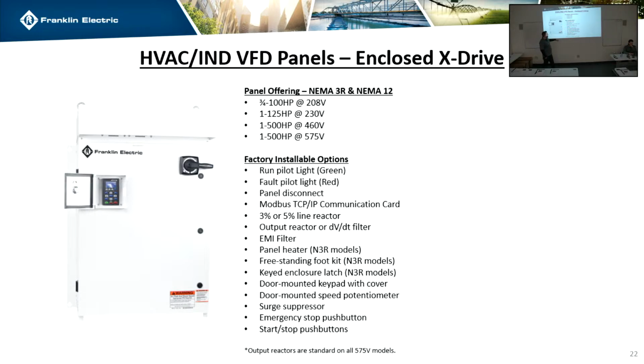Like we were just talking about, we have output reactors and output filters depending on the distance between the VFD and the motor. We have EMI filters if needed. Panel heaters are a big one. The freestanding foot kits. We have the keyed enclosure latches if you want them. We have keypad covers, which is this. We have clear ones, and we have the solid ones that are lockable. We have speed pots. You can also get a speed pot that we have a window big enough that'll fit the keypad and a speed pot in there. Surge suppressors, e-stops, and start-stop controls.